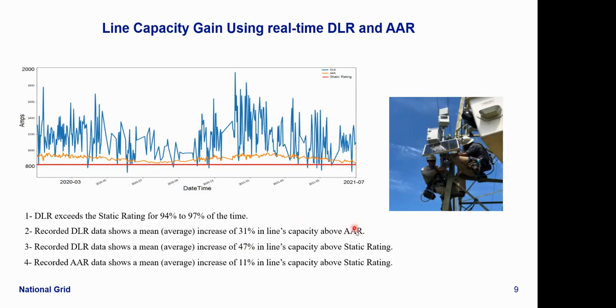We've also done comparisons with the existing AAR processes we use in the system, and DLR still exceeds AAR by 31%. AAR exceeds static rating by just 11%. But look at the difference, 47% versus 11% if we go with dynamic line rating.